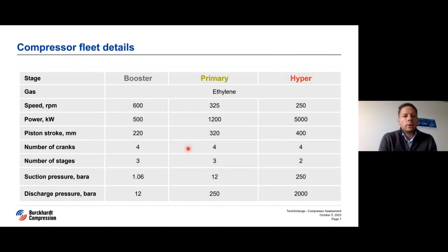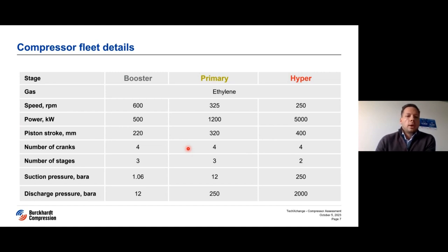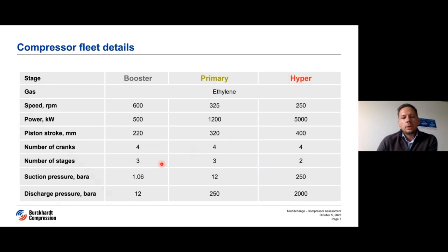These nine compressors in three types are Burckhardt compressors, all compressing ethylene, but their design varies greatly, mainly by size and power. If we speak about the booster, it has 500 kilowatt prime drive power, up to the hyper compressors, the biggest one, with five megawatt power. They are different-sized horizontal opposed compressors with different numbers of stages: three stages for boosters, three for primaries, and two for hypers. What is quite interesting is the wide range of operating pressures — from nearly atmospheric pressure of one bar on the suction of the booster, up to about 2,000 atmospheres on the discharge of the hyper, from which gas is taken to the reactor.